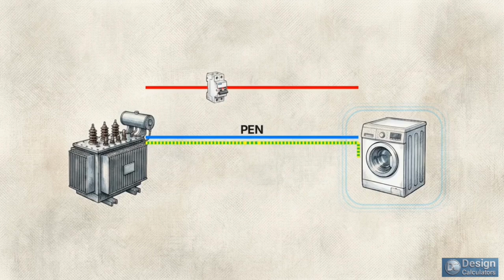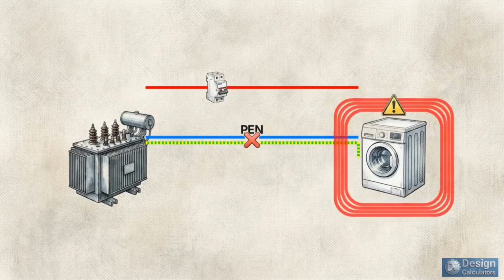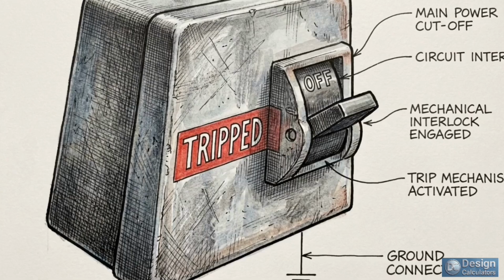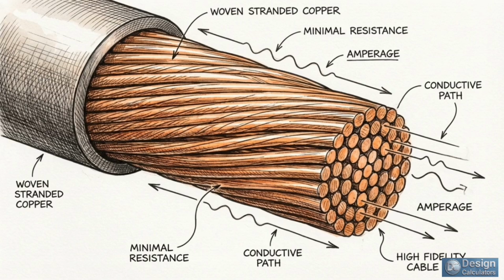Some networks save on expensive copper by using a TNC system, combining the neutral and earth into a single conductor. The trade-off is vulnerability. If that single combined wire physically severs, the safety loop is gone. The appliance casing remains dangerously energized. The TN system accepts the vulnerability of a broken wire in exchange for speed. It uses a low-resistance copper loop to force a high-current, brute-force disconnection.